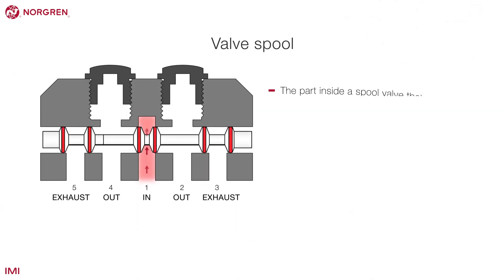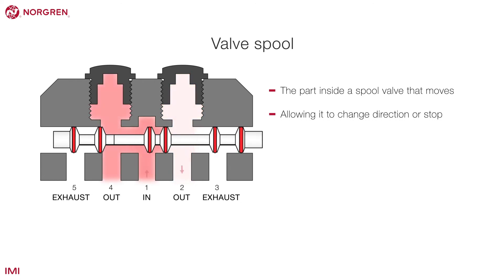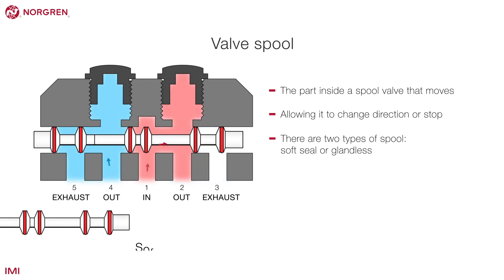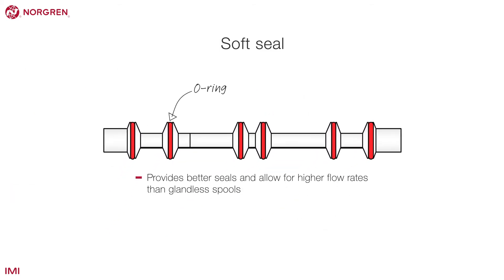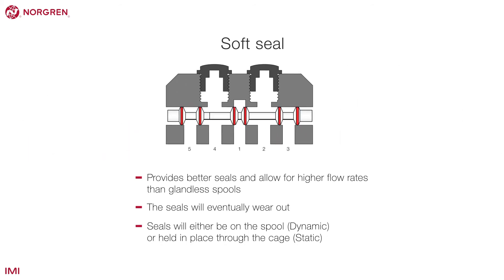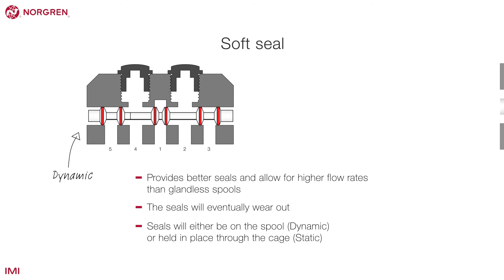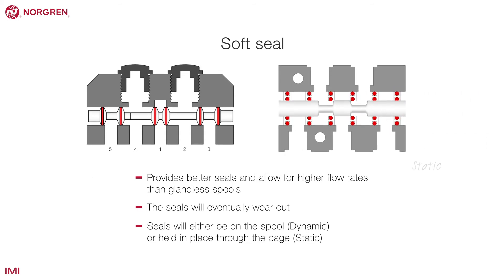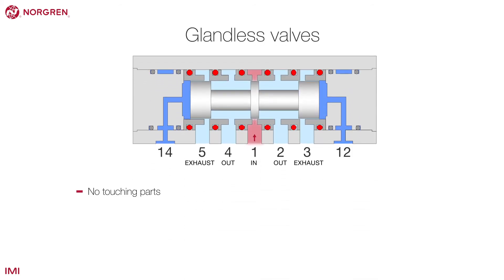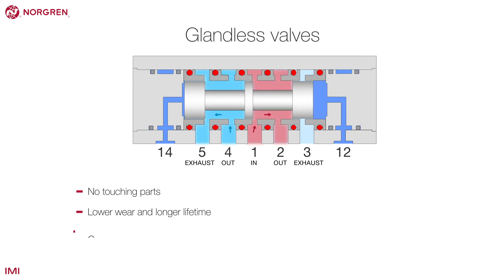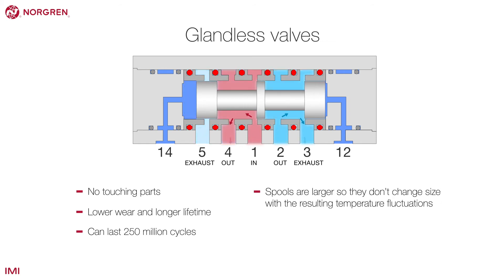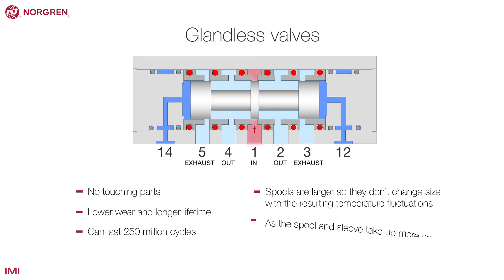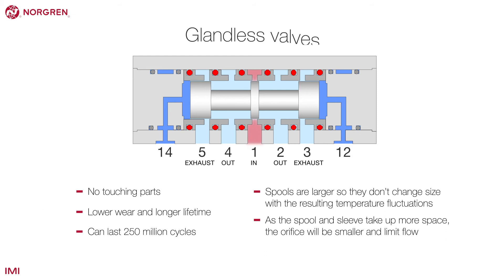A valve spool is the part inside a spool valve that moves, either allowing it to change direction or stop. There are two types of spool: soft seal or glandless. Soft seal spools use O-rings to create better seals and allow for higher flow rates than glandless spools, but the seals will eventually wear out. The seals will either be on the spool — referred to as dynamic — or held in place through the cage, referred to as static. Glandless valves have no touching parts, which means much lower wear and longer lifetime; typically a glandless valve can last 250 million cycles. Tight tolerances mean the spools are larger so they don't change size with temperature fluctuations, but the spool and sleeve take up more space, so the orifice will be smaller and limit flow.